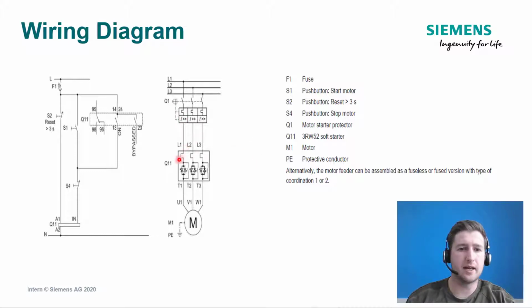Now, as you can see here, downstream of your short circuit protection, you have the soft starter, and then you have the motor starter, and the motor is typically earthed, not the soft starter. Whereas previously on the older versions of soft starter, you could earth the soft starter, now it's all handled through the motor. So in a typical mains feed configuration, you'd have short circuit protection, soft starter, and then your motor, which is earthed.